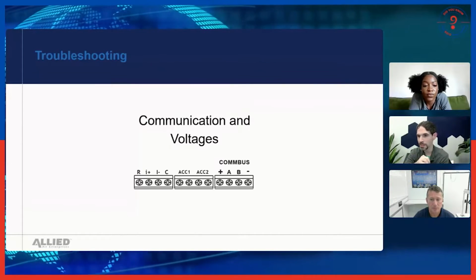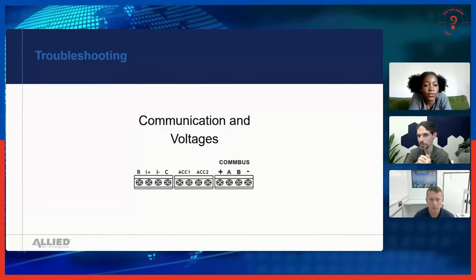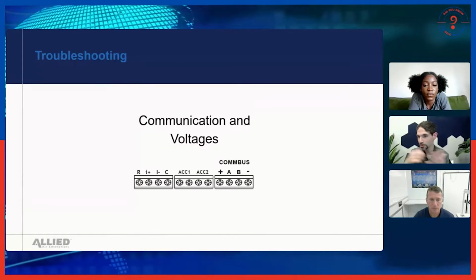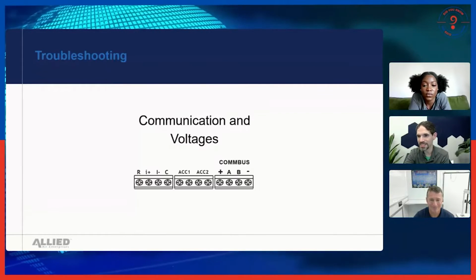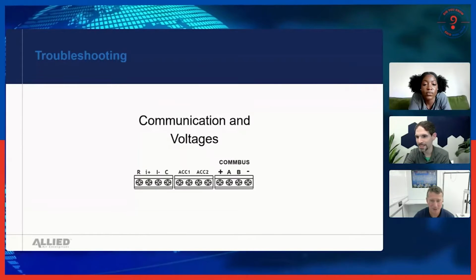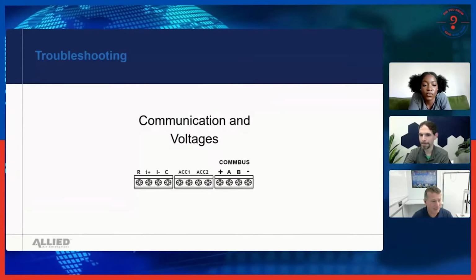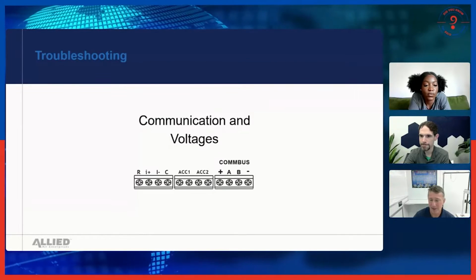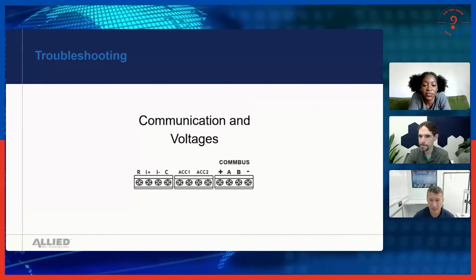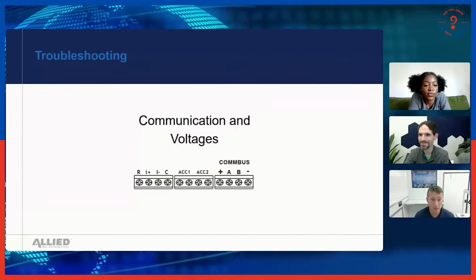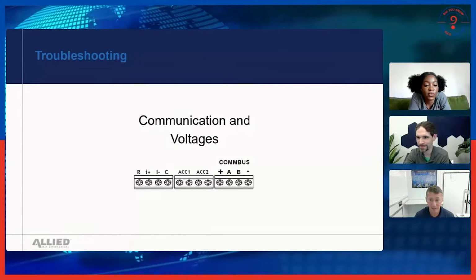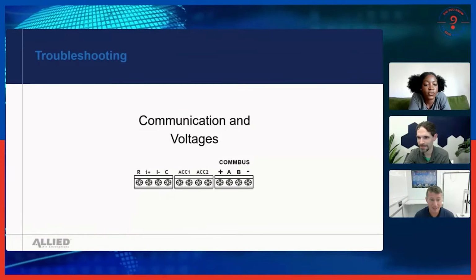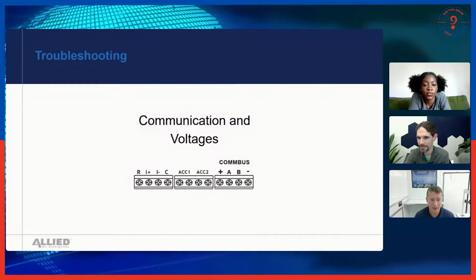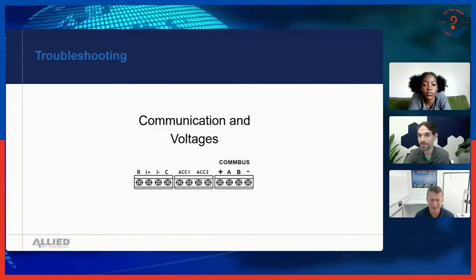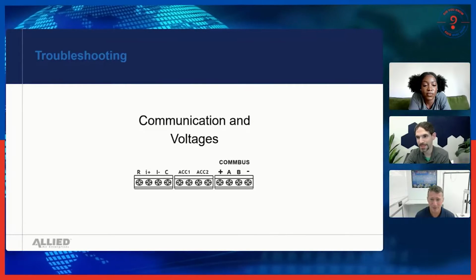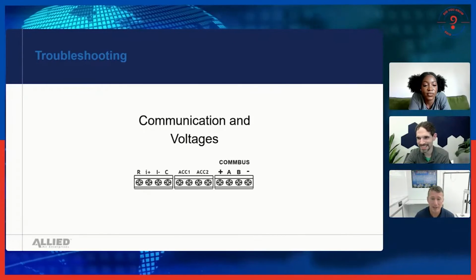And then you've got the power flowing through it to give the controls the oomph to push the demand. So if a technician gets their meter out and sees 4 wires, puts it on volts AC like normal, goes from common to R, and reads 24 volts AC, they think okay, I've got power here.